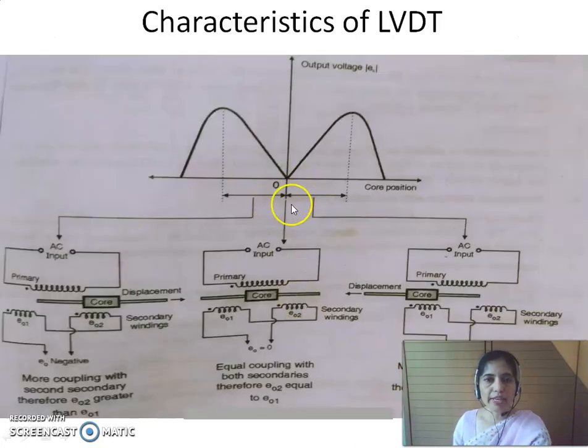This figure shows the characteristics of LVDT. The origin point marks the null position or the center position. That is, if the core is exactly at the center, then the voltage induced in both the secondaries will be identical, hence will cancel out each other, and the output will be 0. But as the core moves towards one secondary, it will induce more voltage in that secondary, and therefore the output voltage will follow the voltage in that secondary coil.